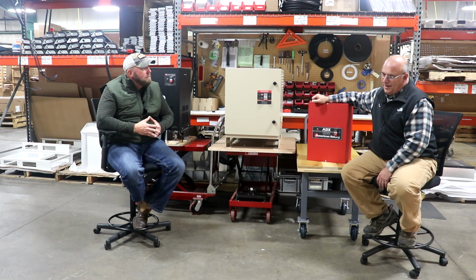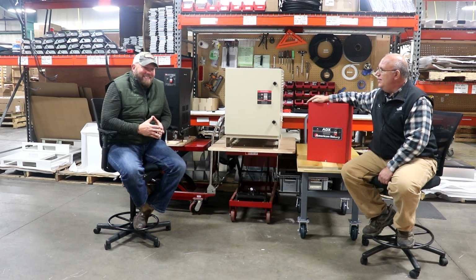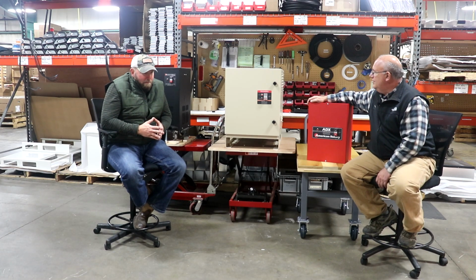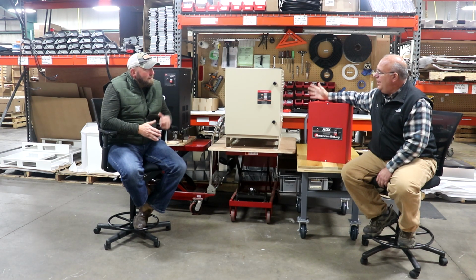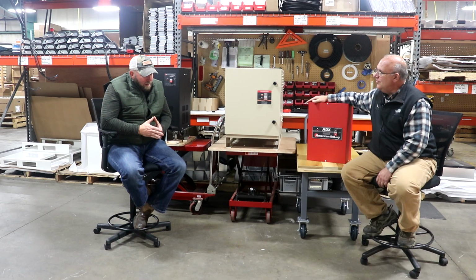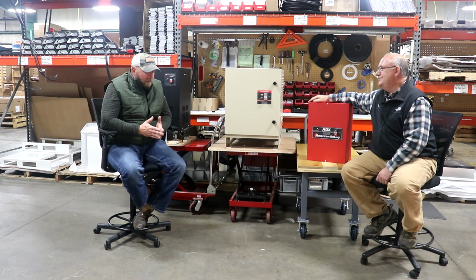Right. Next question that I get all the time is that, hey, I can go out on the internet and I can find plans to make my own phase converter. I mean, all you need is a 3-phase motor and some capacitors and some wire and a motor starter, and boom, I can make my own. So why would you tell someone to buy an American Rotary phase converter rather than just cobbling your own together in your garage? Well, we've been doing this a long time, first of all.